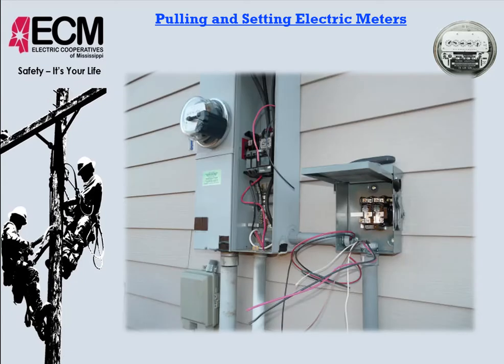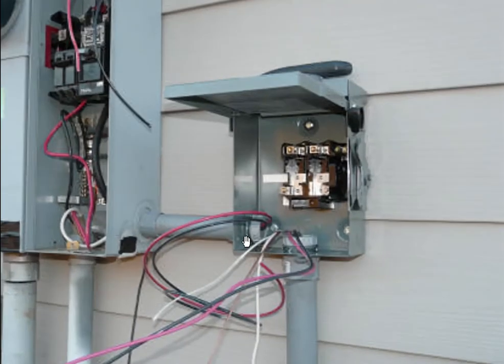Here's an example of something that we could run into. You see here your bottom pipe's probably an entrance cable coming from an underground service. It's going to run up through, there's going to be a channel here on the side that comes around and hooks into the top side. Off the bottom side of the meter comes over here to these breakers, and then you see a knockout there on the side, same metal adapter, lock ring on the inside. See, this one has the metal lock ring right there. Actually, we can expand that just a little bit and get that a little bigger. But see right there on the back side has the metal ring, and then also this plastic nylon bushing that goes on top there, to help protect the wire as we're pulling.